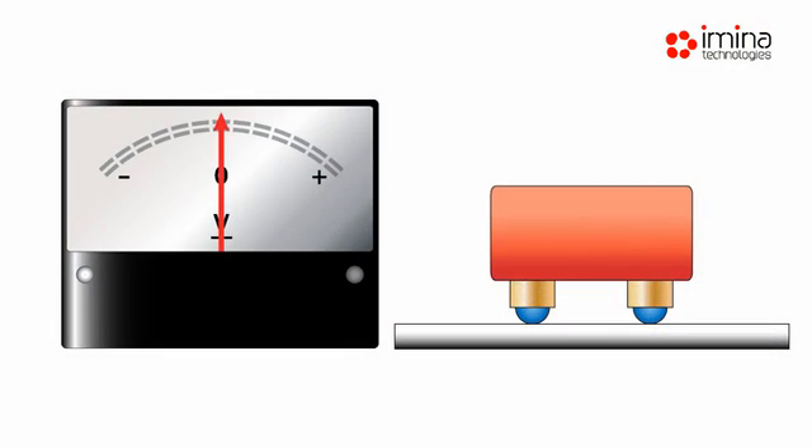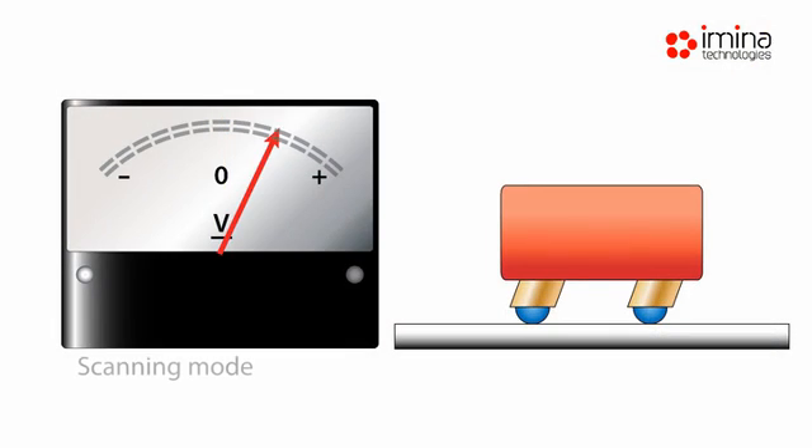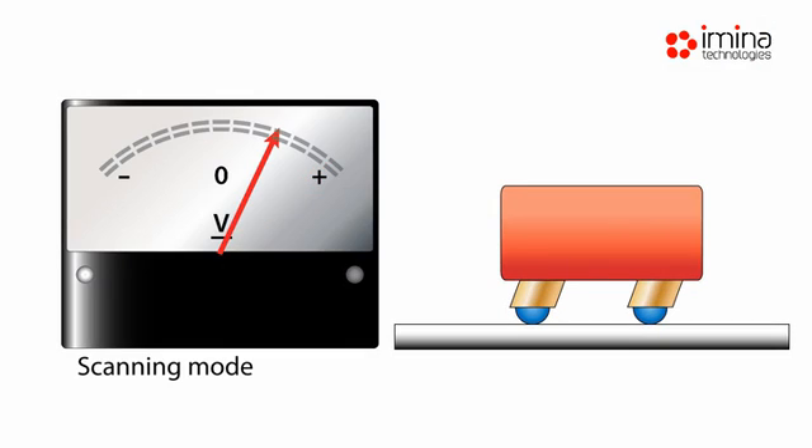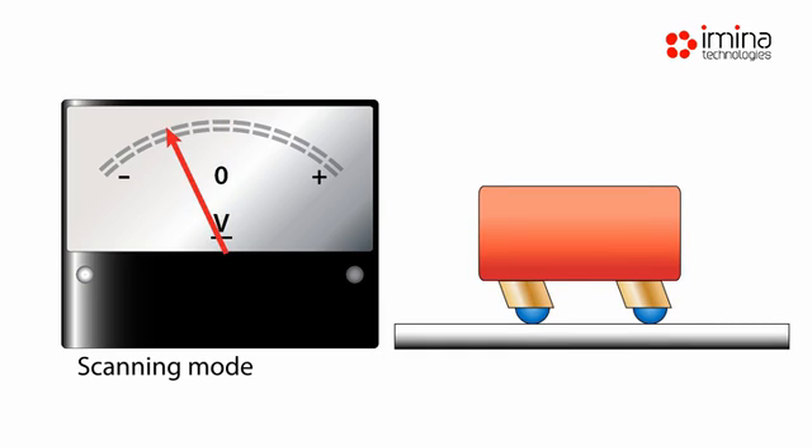In scanning mode, the piezoelectric actuators of the miBot are powered with continuous voltage signals, where the amplitudes define the displacements. To keep the position, the electrical signal must be maintained on the piezoelectric motor.